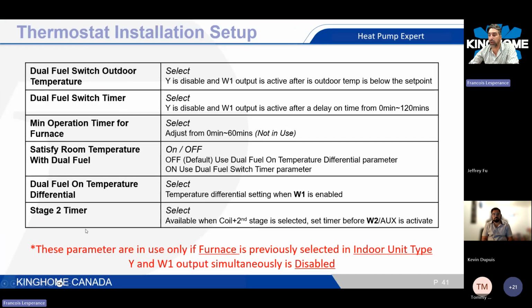We do have the same kind of feature using a gas furnace. So now, when the indoor setting is a gas furnace, Y and W cannot be powered at the same time. Okay, so it will be heat pump, or heat pump off and then furnace on. Dual fuel switch outdoor temperature is there to adjust your balance point, to disable the heat pump and only run the furnace below that point.